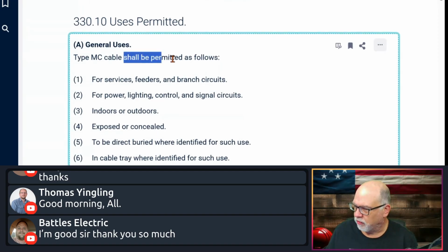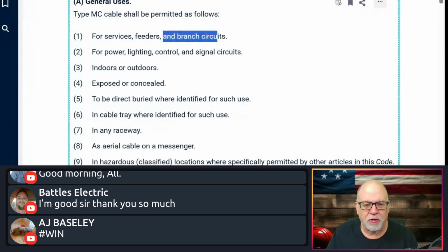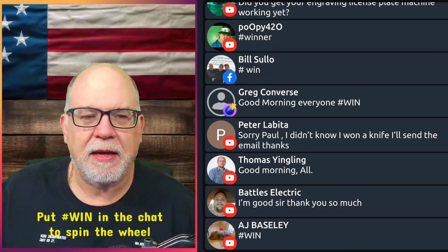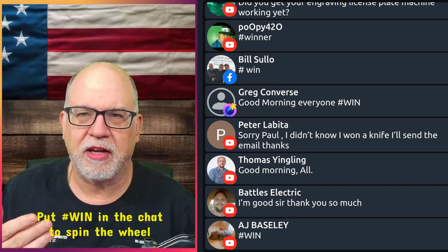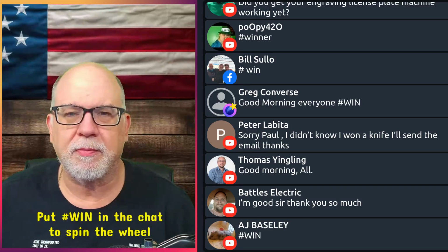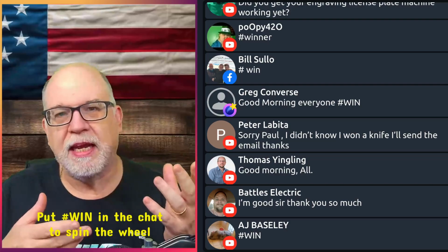Now, type MC cables shall be permitted as follows: for services, feeders, and branch circuits. I see people using MC cable for service applications all the time. The one big caveat here is MC cable. You ready for this? People seem to not understand this, so I'm going to let you know. MC cable is a dry location product. It is not designed to be installed in a wet location inherently if you just have the armor. Even though the conductors inside of it may be rated for a wet location, the product listing itself is not going to lend itself to a damp or even a wet location. It's a dry location product.